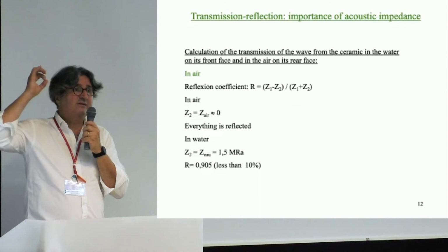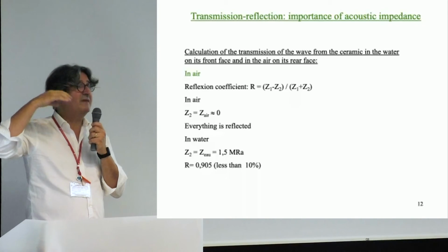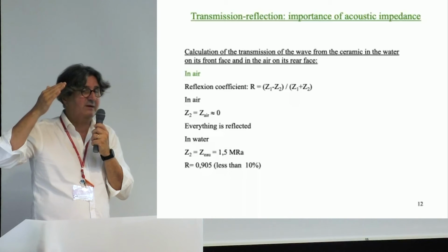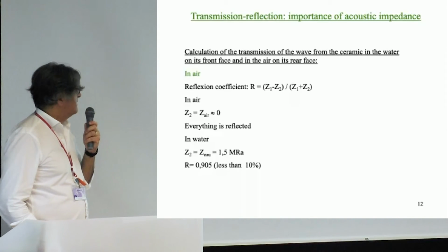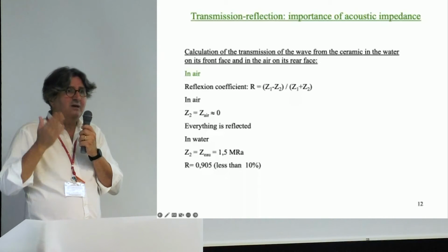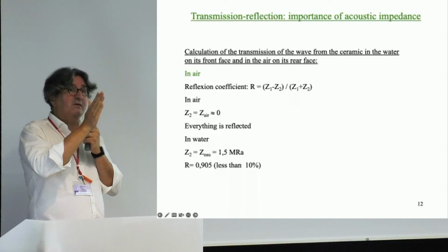The ceramic is 33 megarayls. So you have a 10^5 or 10^6 difference between the two materials, which means that all the energy in air, when you have air on the transducer, is reflected.